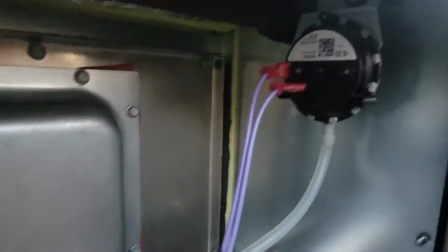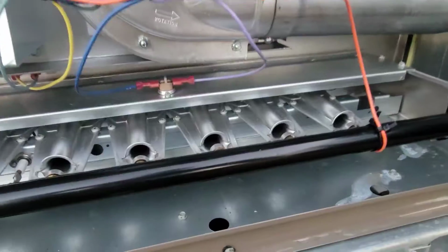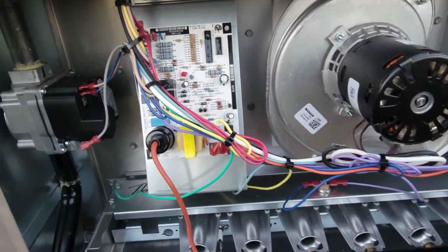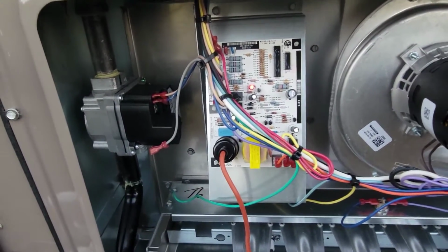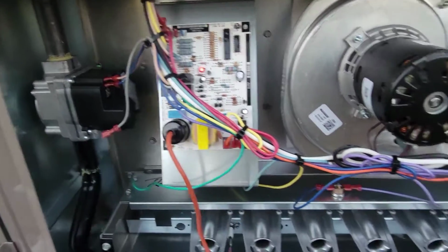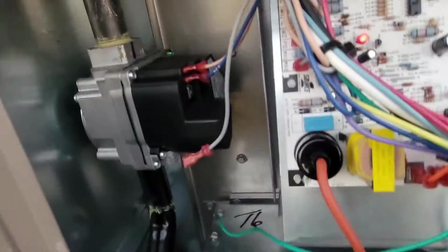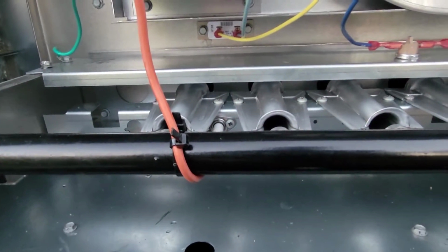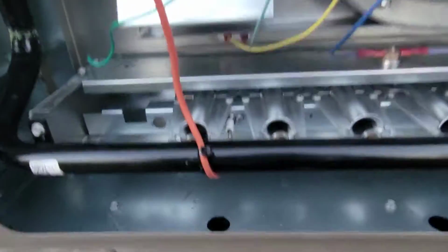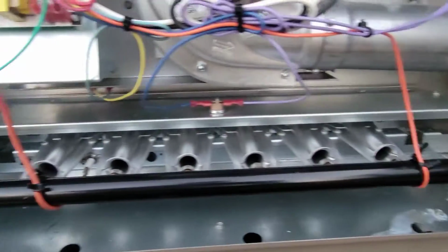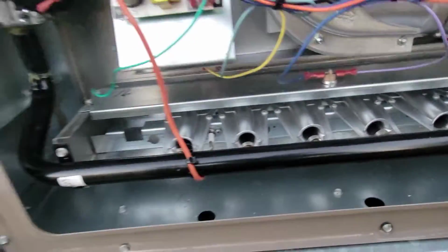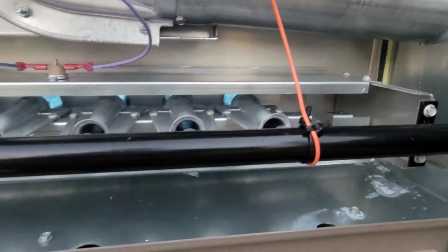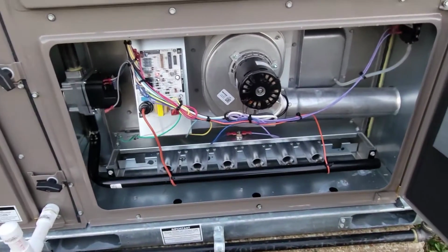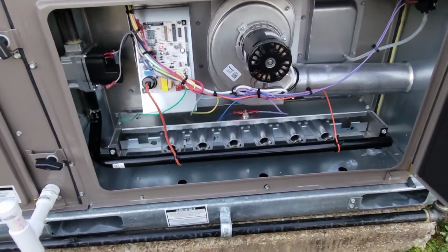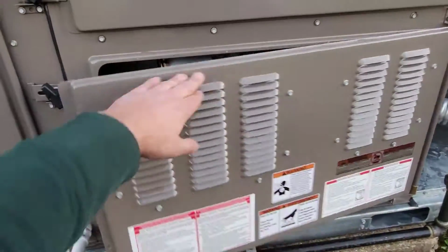It's heating time. Inducer motor comes on, closes the pressure switch. And then the other safeties like the rollout and the limit switch are closed. Make sure there's no codes on the board. And then our spark igniter should fire off. At the same time, we open the gas valve. Make sure it's on. And then our flame sensor's over here. Lights all the way across. Flame sensor sends a signal back to the board saying, hey, we have flame rectification. And that's how you successfully commission this equipment.